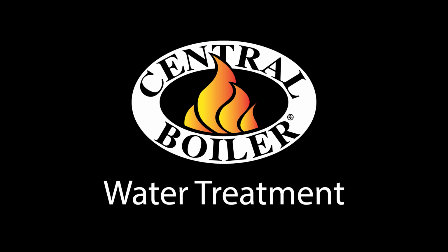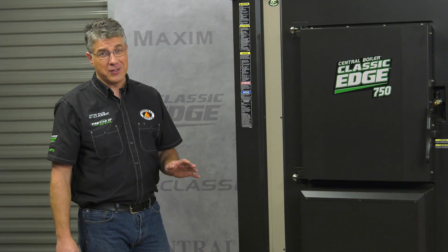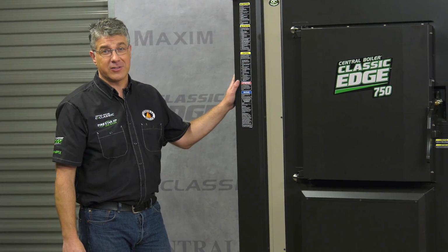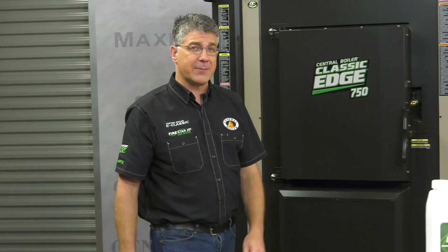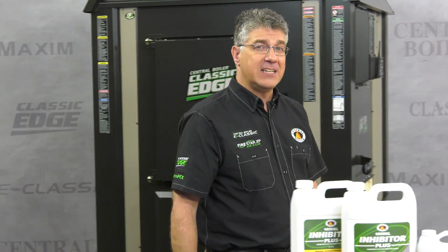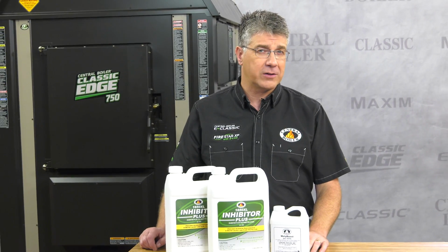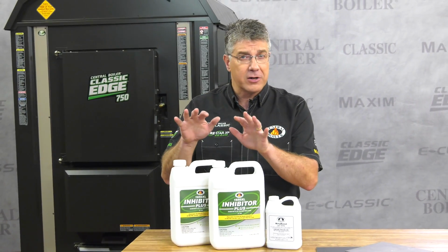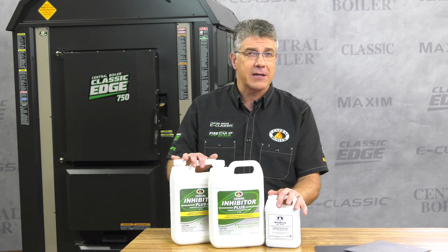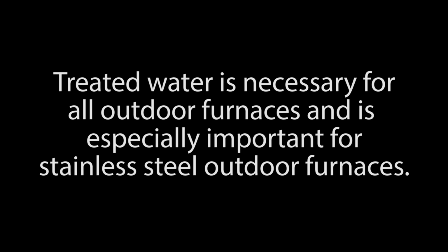Water treatment sounds boring, but it's one of the most important things you can do to protect your outdoor furnace from rust and corrosion. The first few drops that are added to your outdoor furnace need to be treated water. Now, treated water, what that means is mixing your source water with the proper amount of Corrosion Inhibitor Plus and MolyBoost. Treated water is necessary for all outdoor furnaces and is especially important for stainless steel outdoor furnaces.